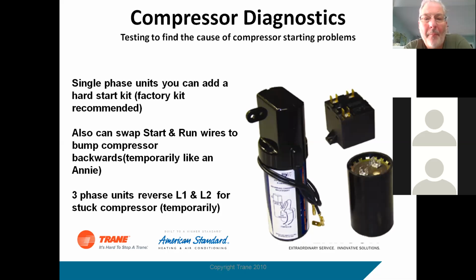All right, on single-phase units, you may find start components, you may find SPP, 6 and 5 hard start kits, you find start capacitors, relays. If you don't have it on there and you're having problems with a compressor that doesn't want to start, say it's got locked rotor or it just doesn't want to bump, doesn't want to move, you can add a hard start kit. I'd prefer that we put a factory hard start kit in here.